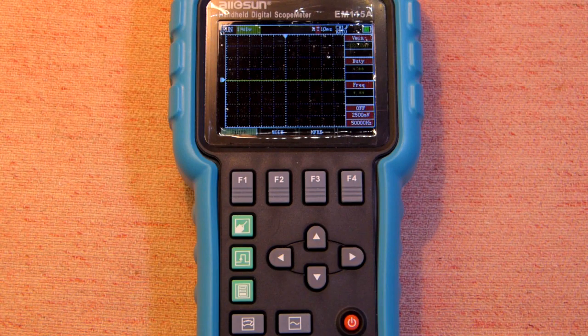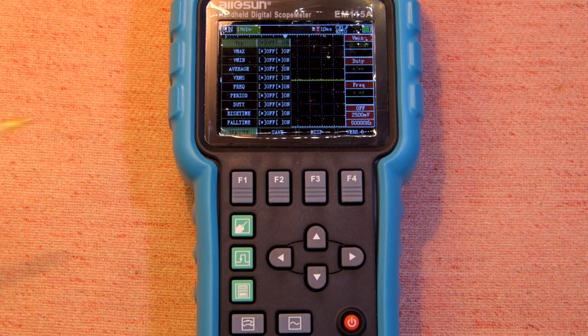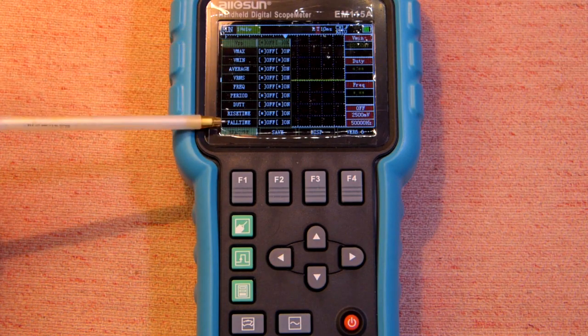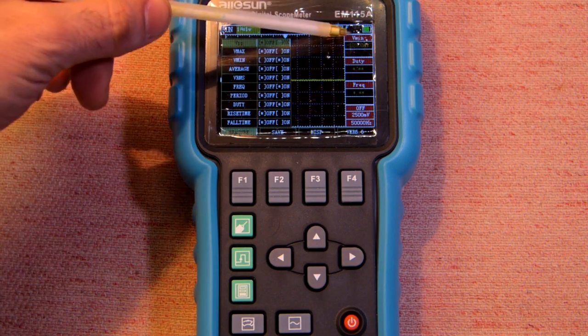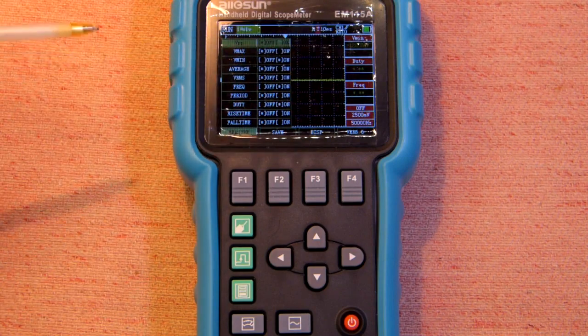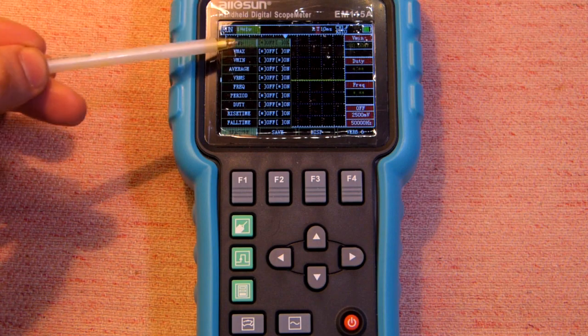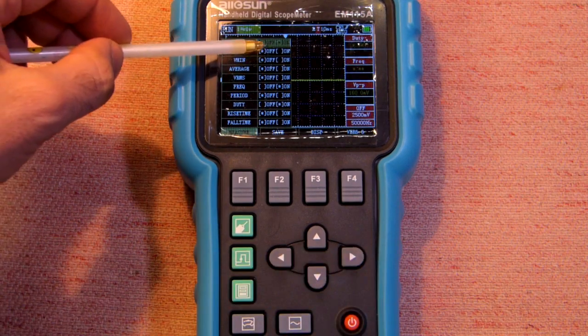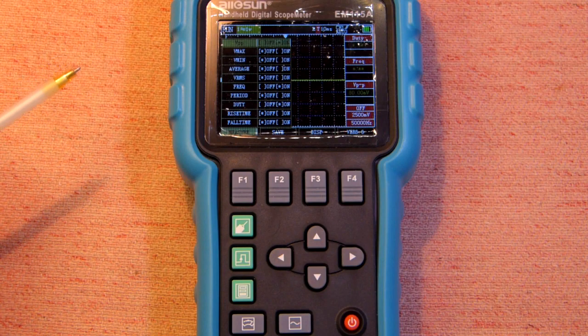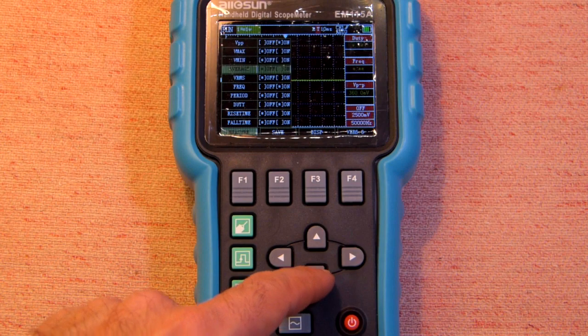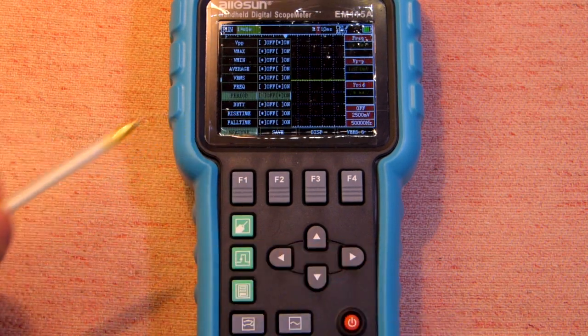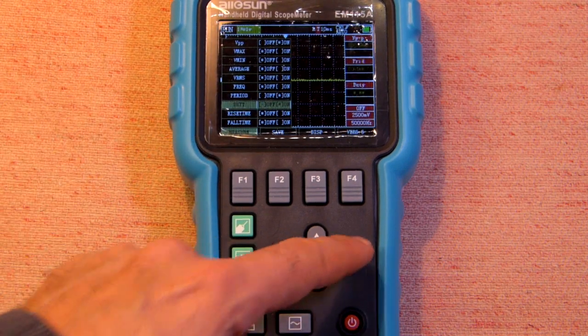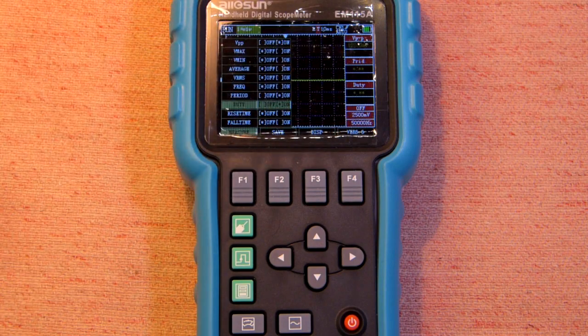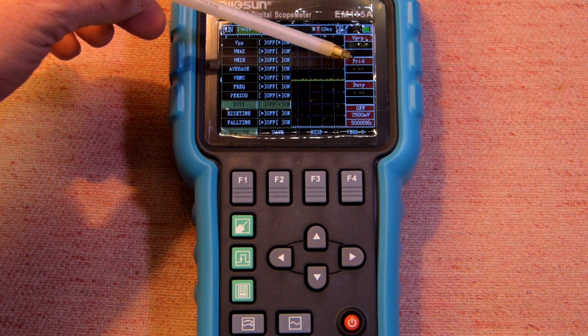As to the third green button, menu, it gives us some interesting possibilities. Measure, F1. Let's press it. With the help of this function, you can display 3 of 10 functions automatically. For example, here we have voltage minimum, duty, and frequency. I would like to get voltage peak to peak. Now it's off. I move it to the right, and here we have it on. I would like to get period. It's off, and I move to it, period, and turn it on. And I would like to have duty. So other functions are disabled, they are off, and here we have the last 3 selected functions: voltage peak to peak, period, and duty.